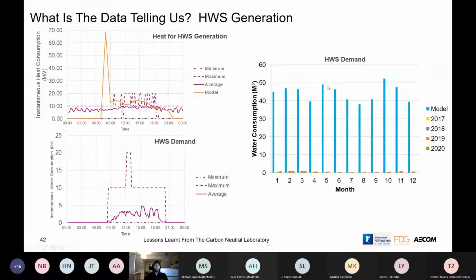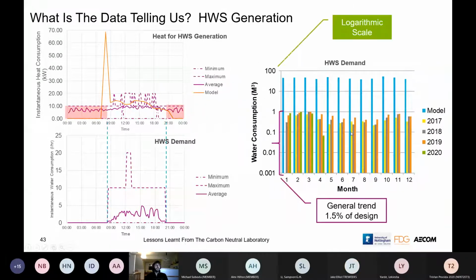The actual hot water consumption - this graph shows the recorded data we got through 2017, 2018, 2019, 2020, which is a fraction of the public health engineers' guidance. I've shifted the graph onto a log scale so you can actually see it. Our hot water consumption is only 1.5% of design, which again leads us back to the thought of local electric hot water heating. Something like that would make more sense because it should be lower embodied carbon, as we haven't got as much distribution pipe work and big central hot water generation.